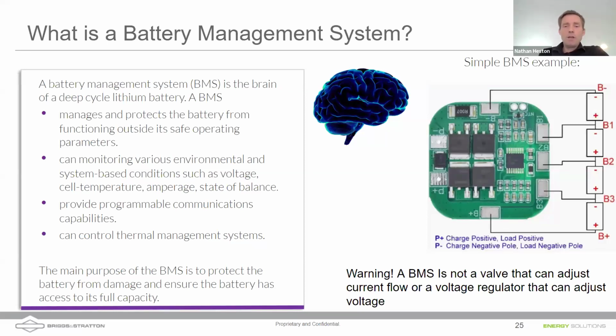But keep in mind, a BMS is not a valve that can control the flow of current, or a voltage regulator that can adjust voltage. It can't do those things. It can request that other equipment adjust those things. A charge controller or an inverter, those are the things which you can adjust the current flow or voltage outputs on. The BMS does not have that capability. All it can do is tell the charge controller, tell the inverter what to do.